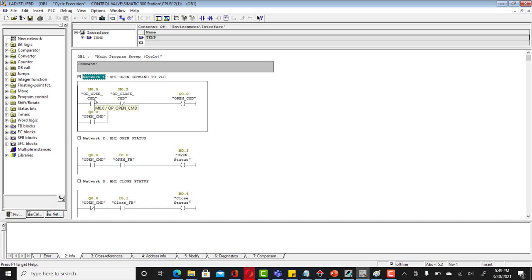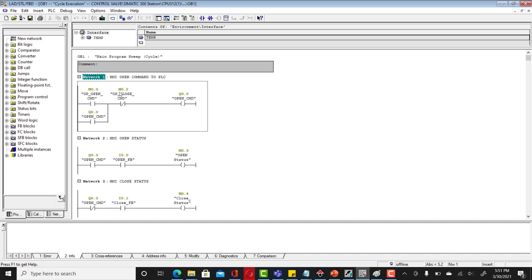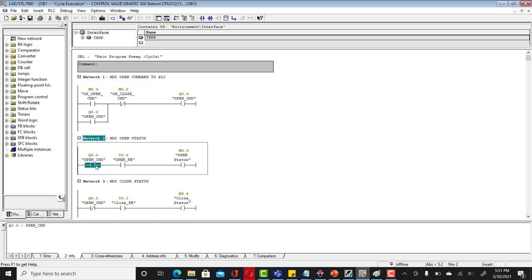If the operator presses open command from an HMI, that would turn high and that would latch that open command. What we did here for open command, we get a feedback of that and we are using a feedback of open command to latch it. If somebody presses a close command from HMI, you're using a normally closed contact here and there would be no supply, so that open command which was actually before high would turn back to zero.